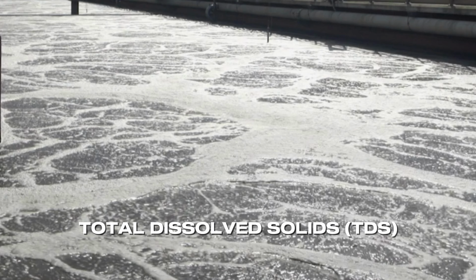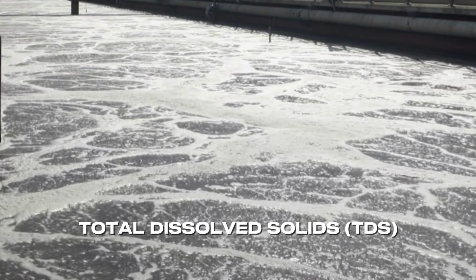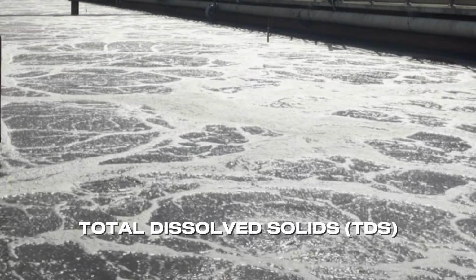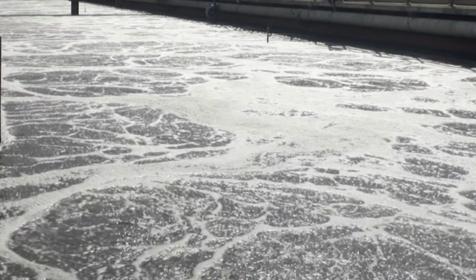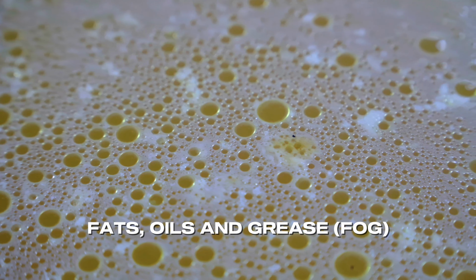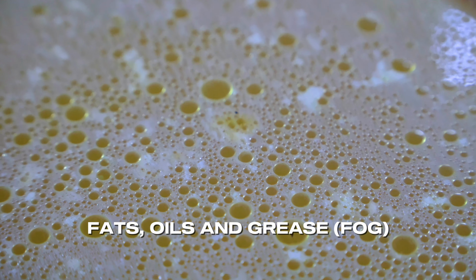On the other hand, total dissolved solids, TDS, such as chloride, sulfates, sodium, and calcium, wage a biochemical war. It creates a hypertonic environment, causing the bacteria to dehydrate, which reduces their ability to treat pollutants and can ultimately lead to cell death. Fats, oils, and grease are one of the most common and destructive components of industrial wastewater.